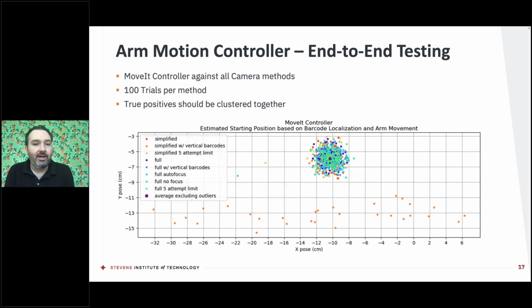One was made available through a framework called MoveIt, which is widely used. But using that controller off the shelf to drive the arm to the desired location to collect measurements had a rather low precision. Trying to deploy the arm under different parameterizations of both the controller and the computer vision algorithms used to identify key targets on the pothead compartment panel, some algorithms failed outright due to how the computer vision was parameterized. We still had a lot of variability in deployment of this controller, with a range of about 4 centimeters in terms of where the arm would actually end up making contact with the panel. Being within that 4 centimeter diameter sphere was a little too much error.